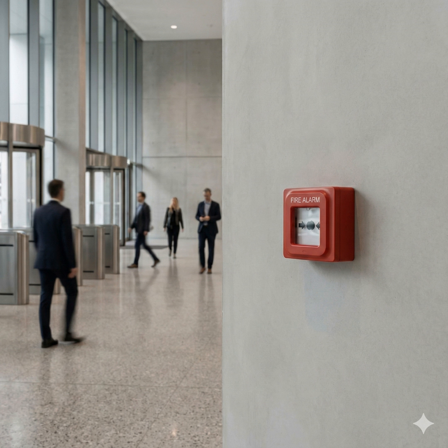They do. Sometimes they're necessary within the fire alarm network itself because they can be optimized by the manufacturer for speed, for signal integrity, for high throughput, all things that are critical when milliseconds matter. So the trade-off is often between highly optimized performance within one ecosystem versus maximum compatibility across all the different equipment in a building. Let's dedicate some serious time to the sensors. I mean, if the control panel is the brain, the detection technologies are the sensory nervous system. If the sensor is poorly selected, or it fails, the brain gets no signal and the whole network is useless.